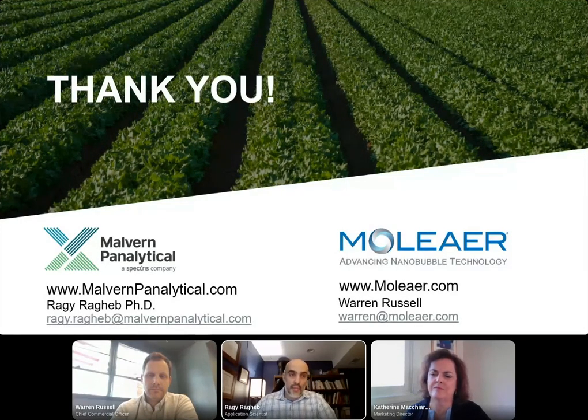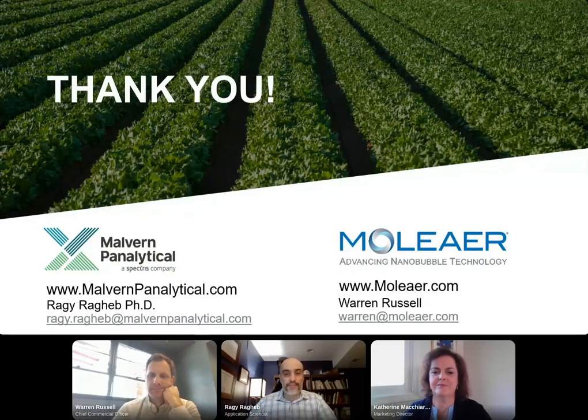It depends on what else is around with your nanobubbles that you want to tease out, and you can tease that out by fluorescence. You can choose any of our laser modules with the corresponding fluorescence filter, depending on what the material might be. Because of the unknown, this particular customer ended up getting all 4 laser modules with all the filters, just to accommodate whatever might be in the water.